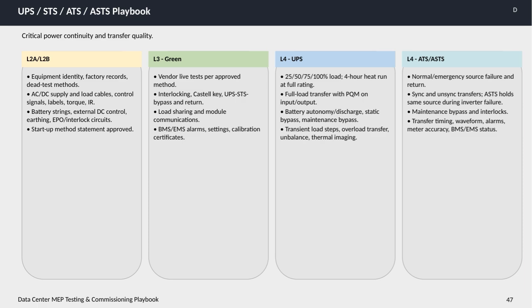For level 4 testing of ATS and ASTS systems, we test normal and emergency source failures and returns. Both synchronized and unsynchronized transfers are evaluated, with ASTS specifically holding the same source during inverter failure to maintain power stability. Maintenance bypasses and interlocks are verified, and we carefully monitor transfer timings, waveform integrity, alarm functions, meter accuracy, and overall BMS and EMS system status. Overall, this playbook ensures comprehensive testing to guarantee reliable power continuity and quality transfer across critical data center power infrastructure.